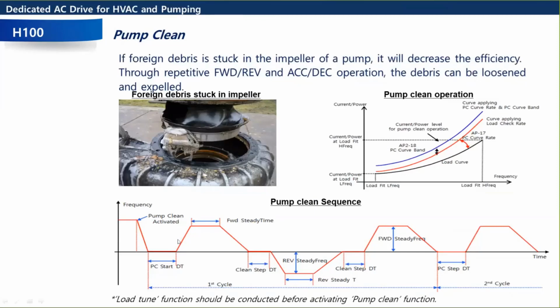And down here, you can see how the operation is going to work, or the sequence. Let's say you flip a switch, pump clean goes active. There's a delay time. It runs forward for a certain amount of time. Then it stops, runs reverse. You can set the frequency. You could set the delay time. You could set how long. And then you could also set how many times you want it to run back and forth. So it's all fully programmable. There's almost a whole parameter group, I think it's the AP2 group, that shows how to set this up. Pretty easy to set up and pretty versatile. Again, these functions are standard on the drive to eliminate external equipment. You can just program it right into the VFD.